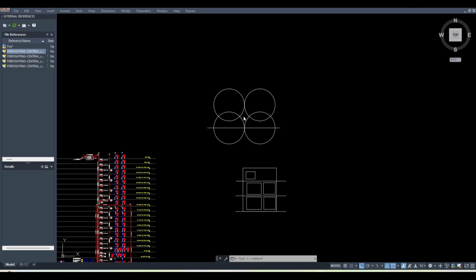Now once again I'm repeating it. The wall to sprinkler distance: not less than 100 mm. The wall to sprinkler maximum distance cannot be more than 1.8 meter. Sprinkler to sprinkler distance cannot be more than 4.5 meter. Okay, and then yeah, that's it, right?